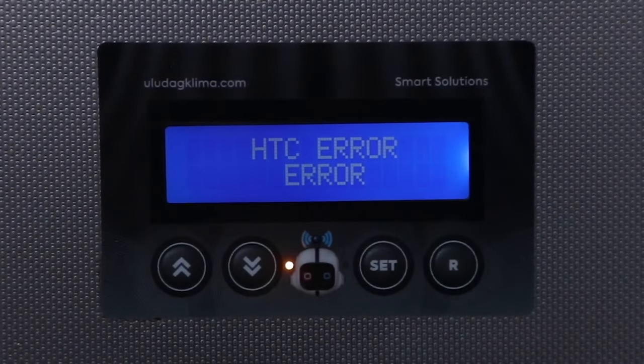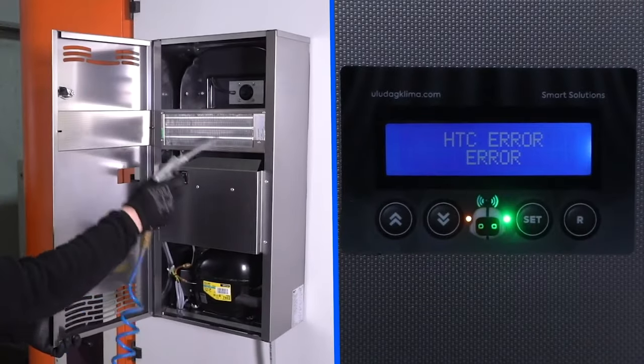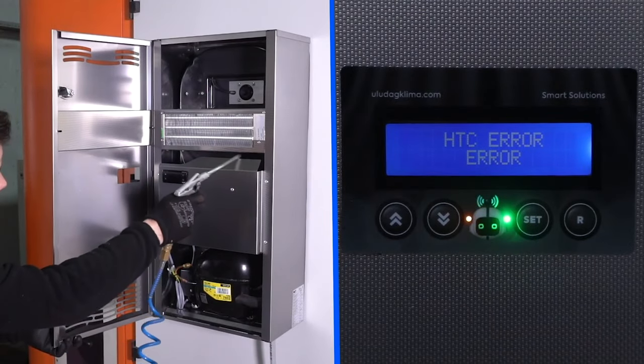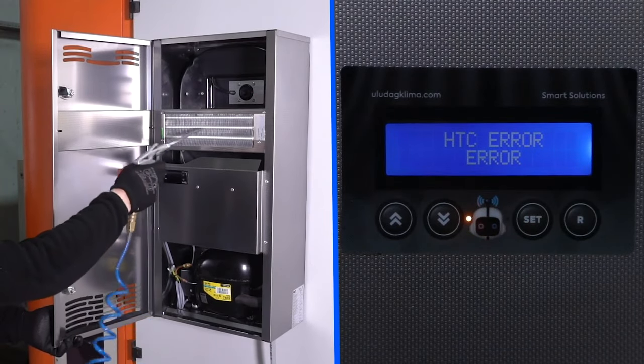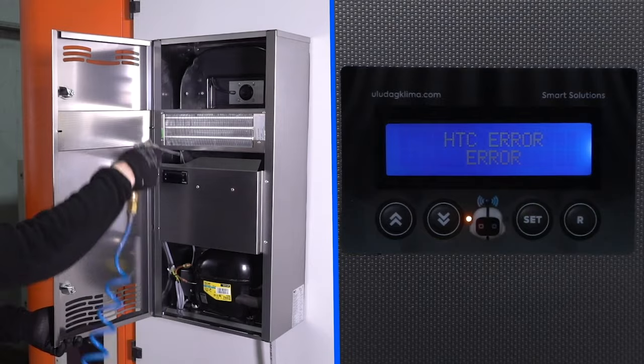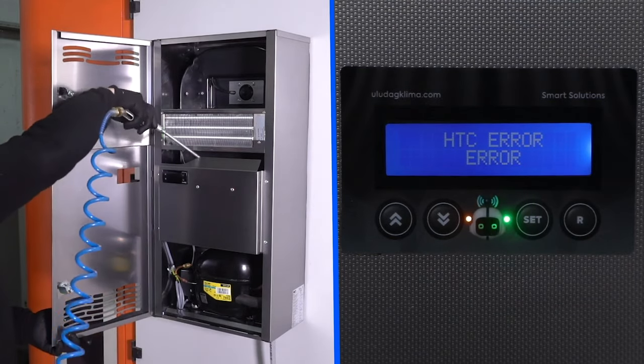HTC fault occurs when the condenser surface is hotter than it should be. This could be due to excessive dust, dirt on the condenser coil, or a faulty condenser fan. Opening the front cover and cleaning the coil resolves this issue.